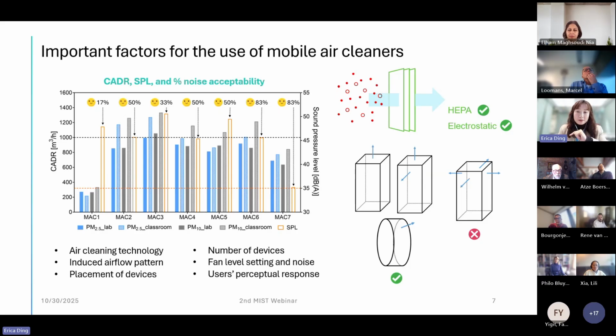Regarding fan level settings and noise, previous studies have recommended a ventilation rate of 8 to 10 liters per second per person for good indoor air quality. For a classroom with 30 students, that means approximately 1,000 cubic meters per hour. If 1,000 cubic meters per hour, marked by the black dashed line, is the desired CADR level, then most mobile air cleaners need to run at their maximum fan level to achieve this goal, or try to.